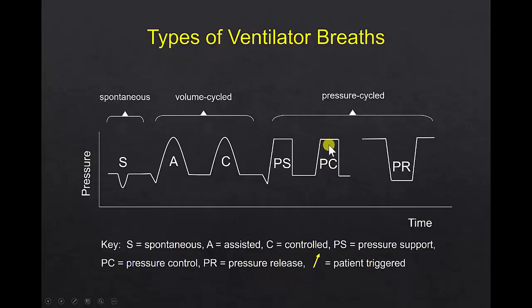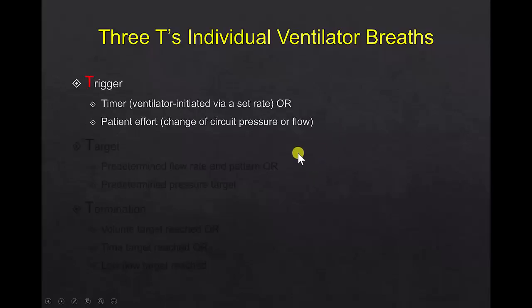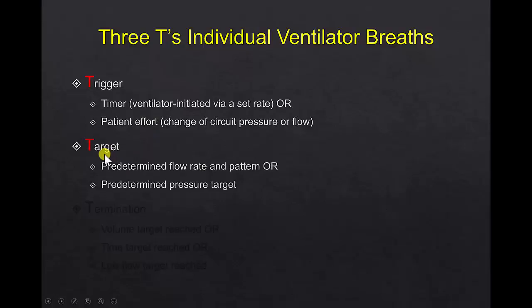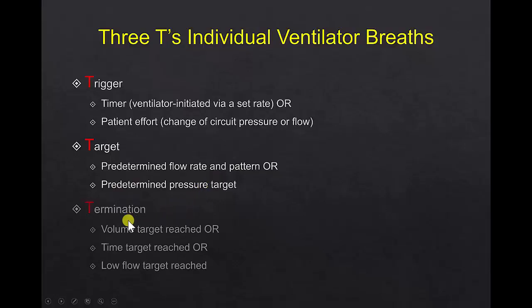Three of these breaths are triggered by the patient — a spontaneous breath, an assisted breath, and a supported breath — while the other three are machine-triggered by a timer. The three T's of individual ventilator breaths are: Trigger — what starts the breath, either a timer or the patient's effort; Target — either a flow rate and pattern or a pressure target; and Termination — when the volume is reached, time is reached, or the flow drops to a critically low value indicating the patient has finished inhaling, as seen in pressure support ventilation.